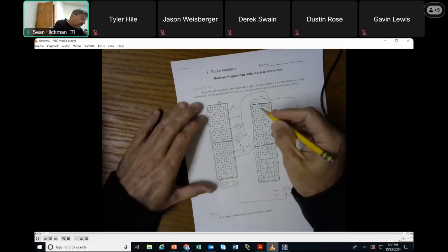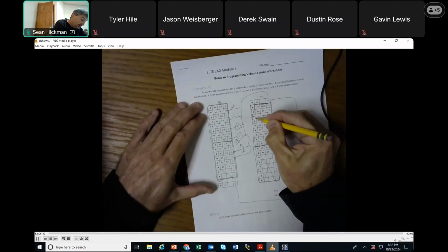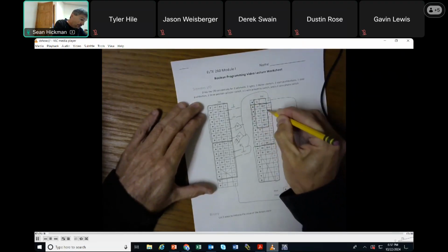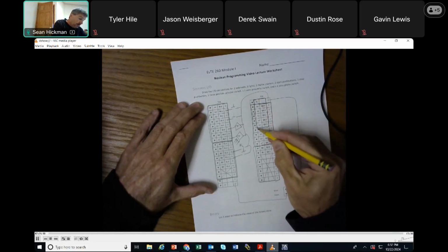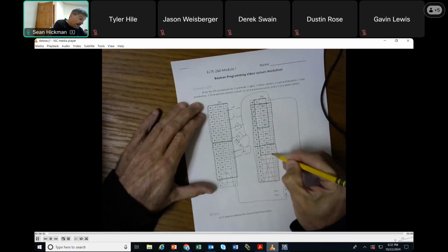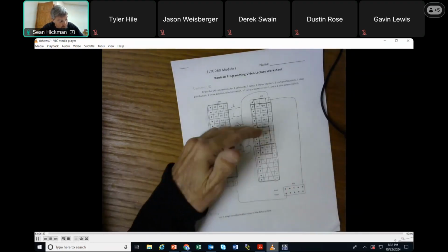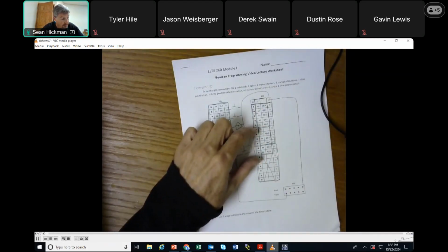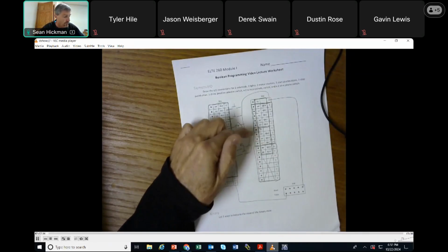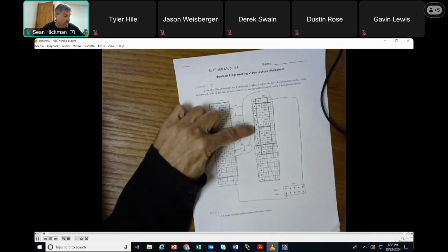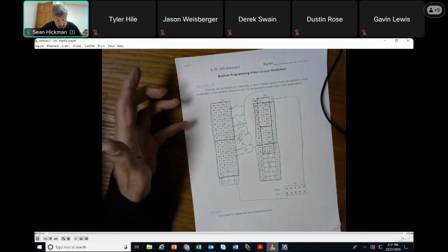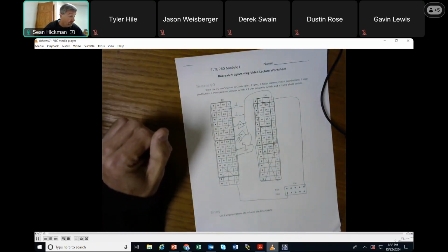So the first one is right here. 1L sources up to Q.4. 2L sources the next group of 5. So the problem is the sourcing of 1L and 2L overlap and run over the first byte, because they're grouped by 5, but the byte is 8 long, which could end up being a little confusing.